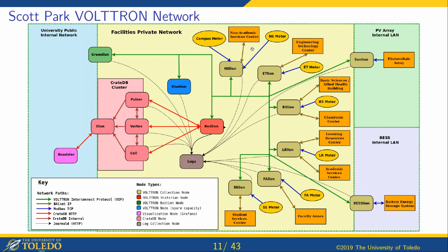Each of the ones in this arc is handling one building-level meter and 1 to 2 buildings—that is, 1 to 2 field panels within the building automation system—and are pulling data from the meters over Modbus and from the building automation system using BACnet.